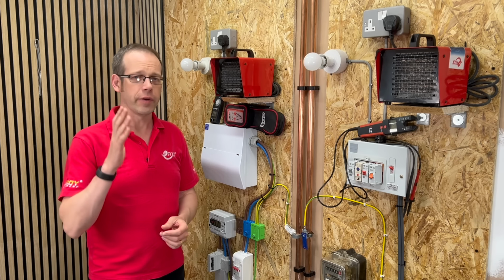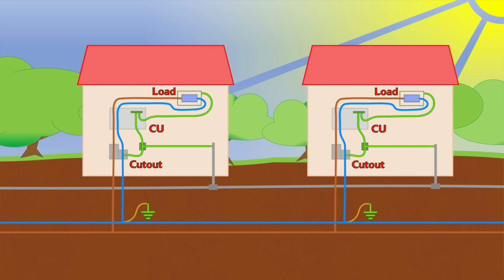Let's look back at scenario 1 with properties connected together as we've discussed, with supply cables on a TNCS system and a common metallic water pipe. Current will naturally flow through the earthing and bonding arrangement, and that's because when the current gets to the combined neutral and earth connection, it has multiple paths it can take back to the transformer. It can flow down the CNE conductor here, as you'd expect, but it also has a very low impedance path it can take along the bonding conductor to the water pipe, through next door's bonding conductor, main earthing terminal, and their CNE conductor as well.